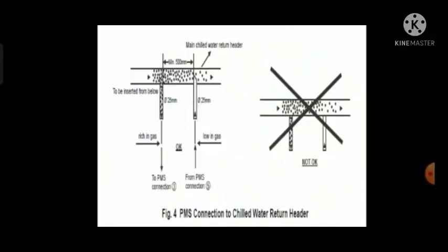Now one more thing, while connecting this tapping pipe, inlet and outlet both. The normal general practice of taking out a tapping from the header is on your right hand side, which is not correct in this case, because here the tapping must enter inside the header and be cut at an angle of 45 degrees towards the water flow direction. Why it is inserted, I will explain to you.